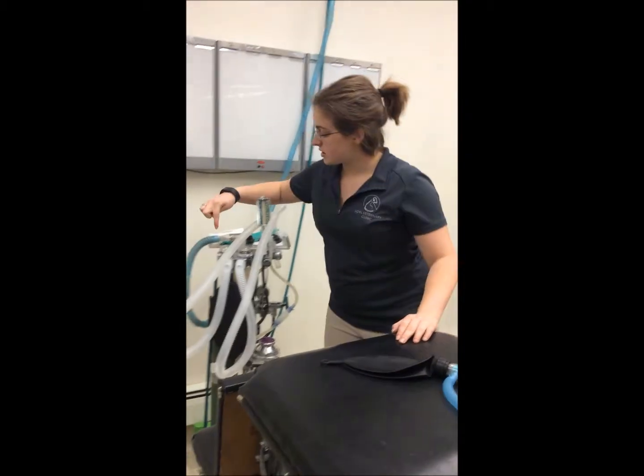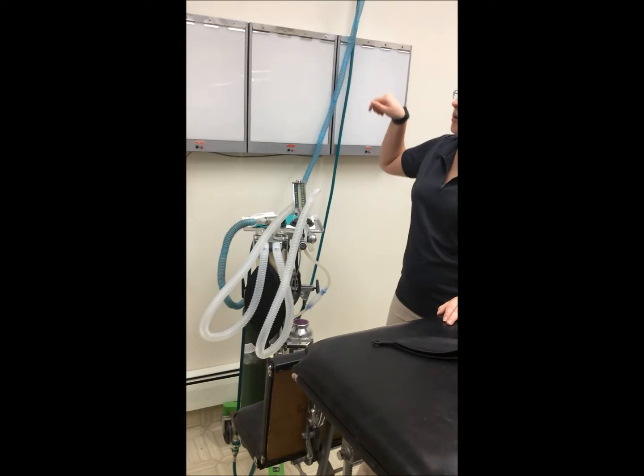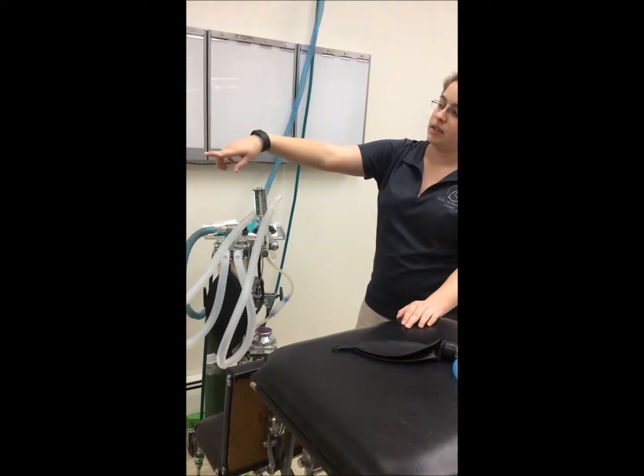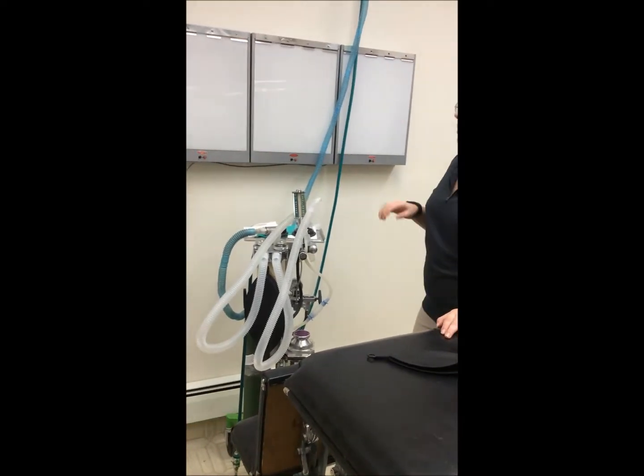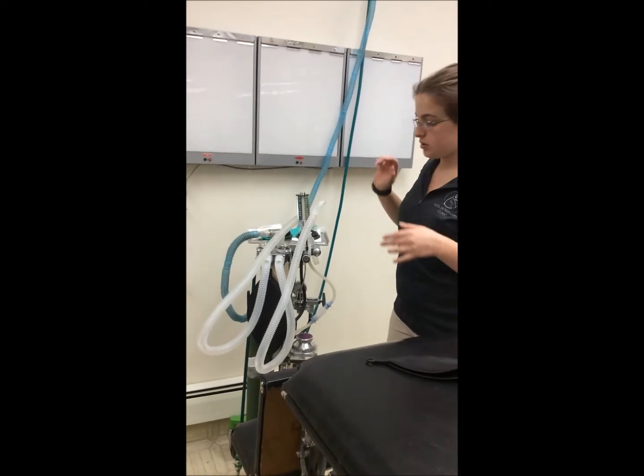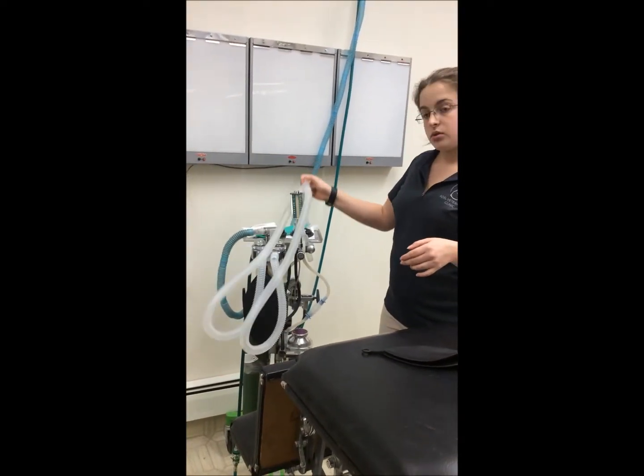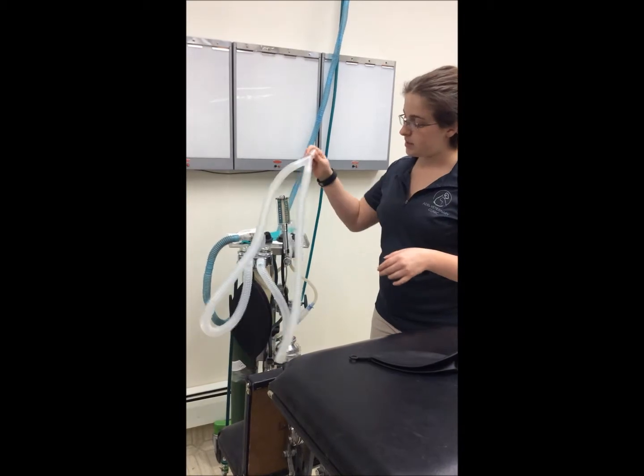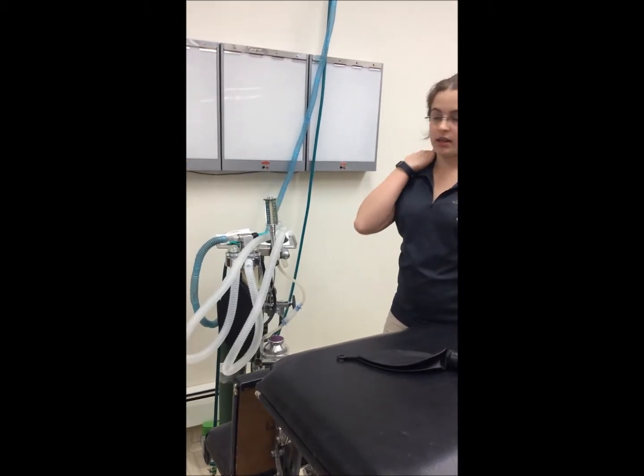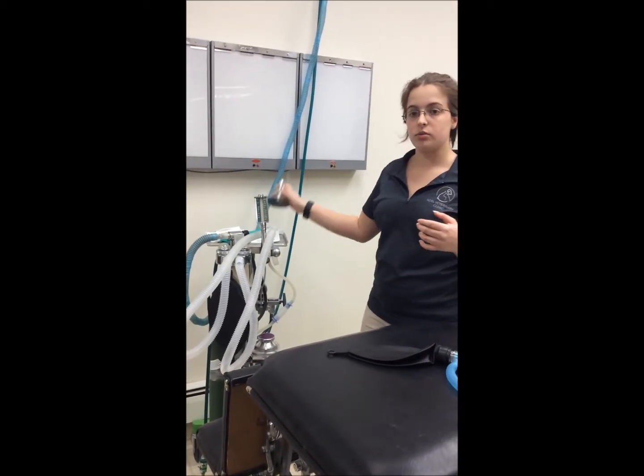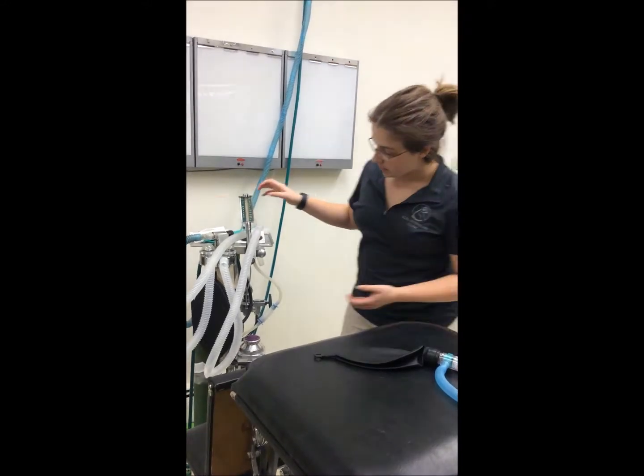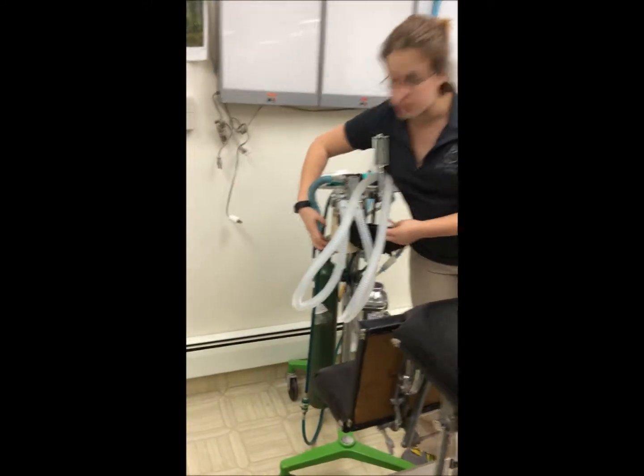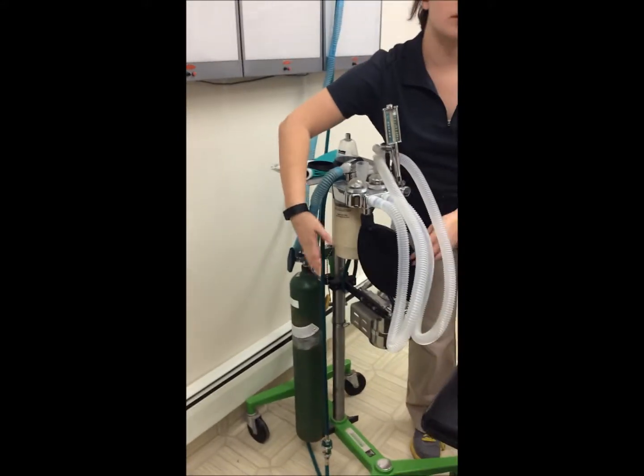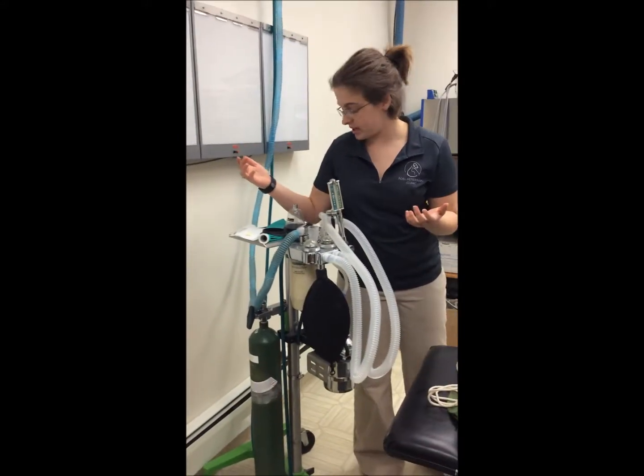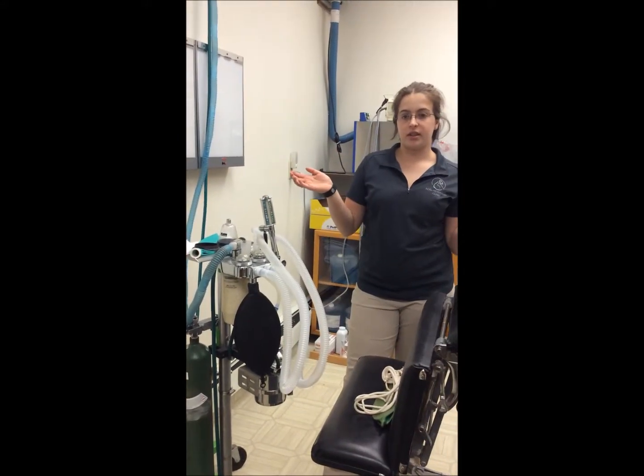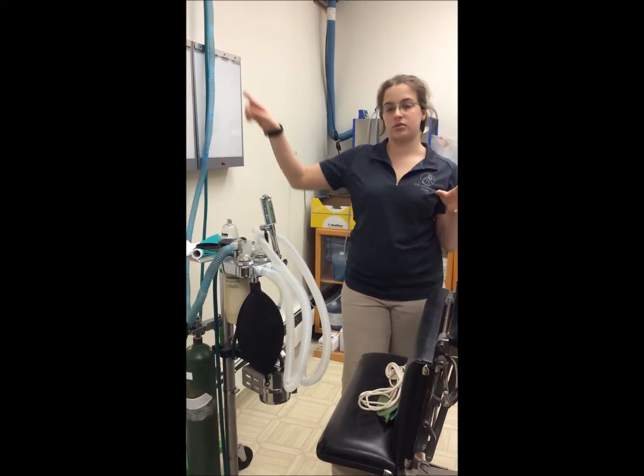We have our scavenging system, which pumps gas out of the building, with an exhaust fan in this corner to help push it out. We have our breathing tubes and a Y-piece that connects to the trach tube or one of the cones. On this side is our CO2 absorber, which absorbs the carbon dioxide the patient breathes out, which then goes through the scavenging system.